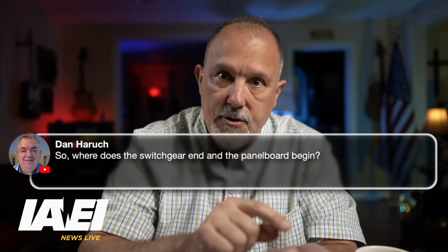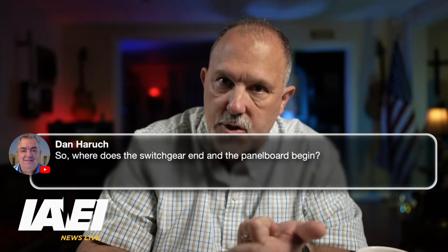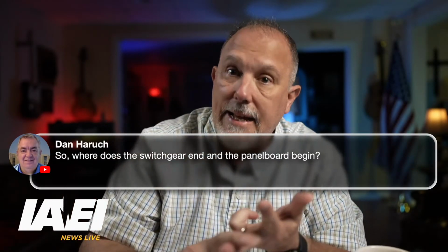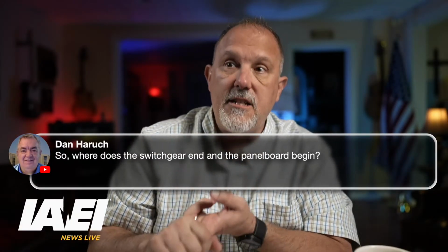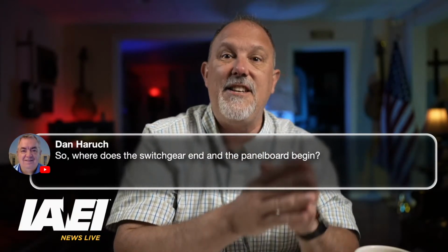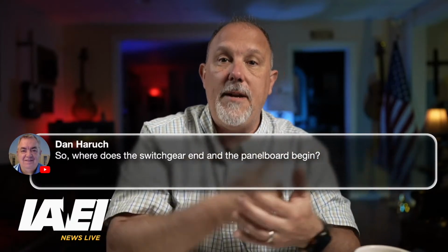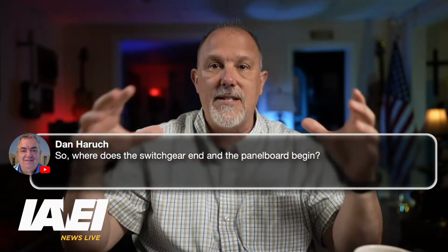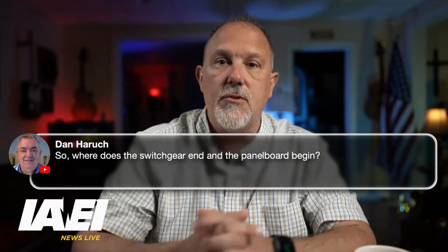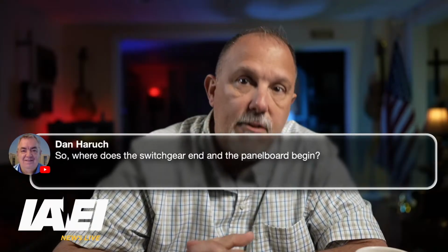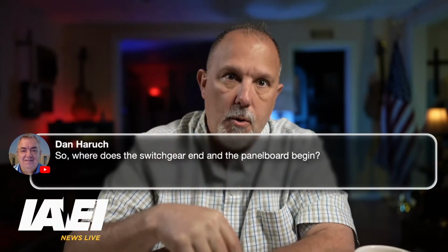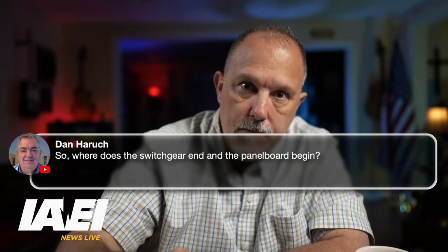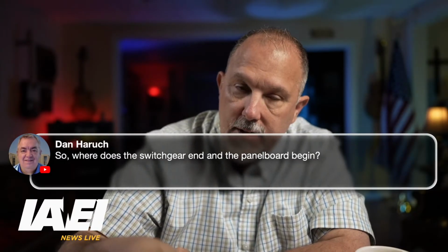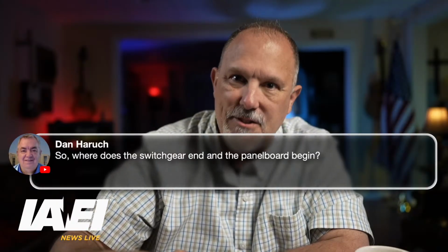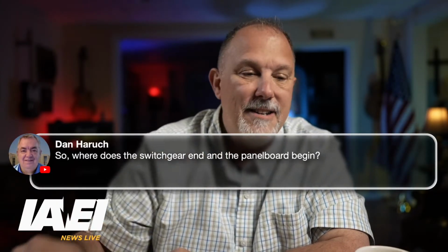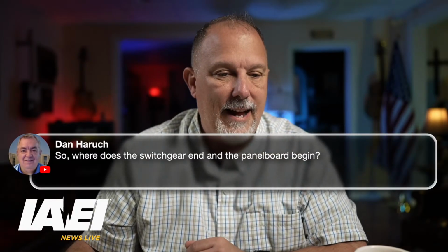There are circuit breakers in a switchboard—molded case circuit breakers and insulated case circuit breakers. They don't cease to be circuit breakers listed to UL 489 once you put them in a switchboard, but when they're in the assembly, the overall assembly is a switchboard, and the components are still listed to the standards they're listed to. A panel board can be put in a switchboard, but it's still a panel board, and inside that panel board will be molded case circuit breakers and possibly fusible switches. So all of those are listed as such.